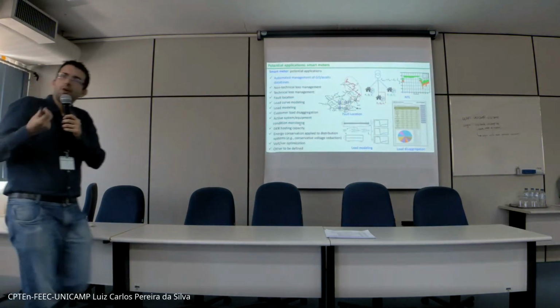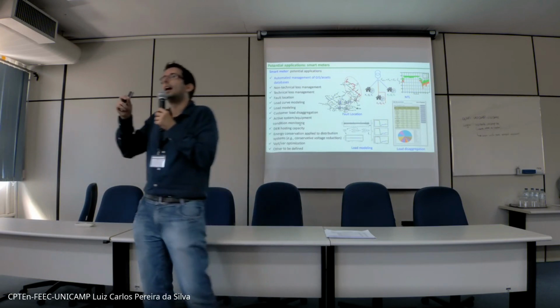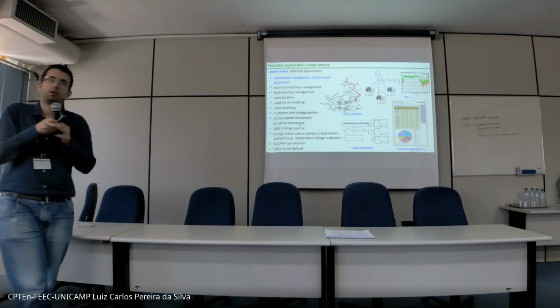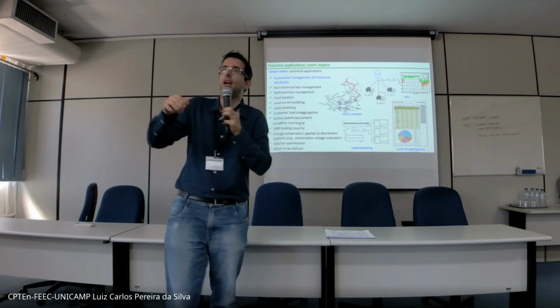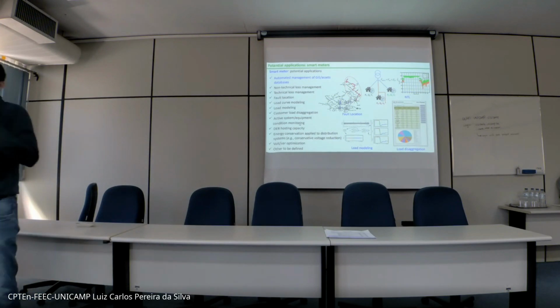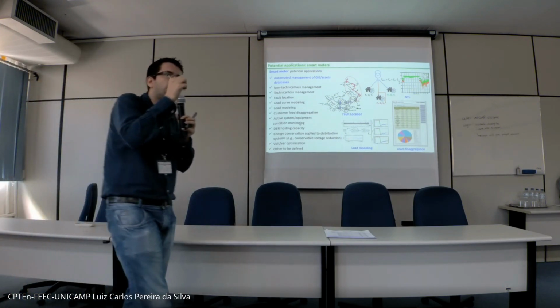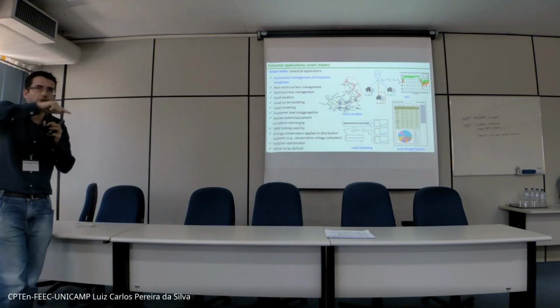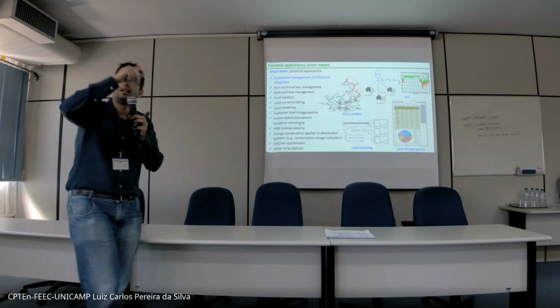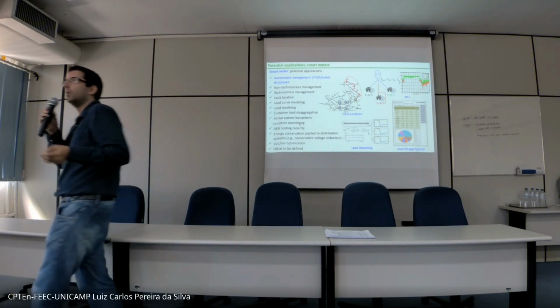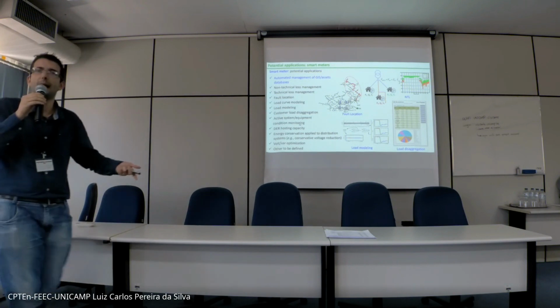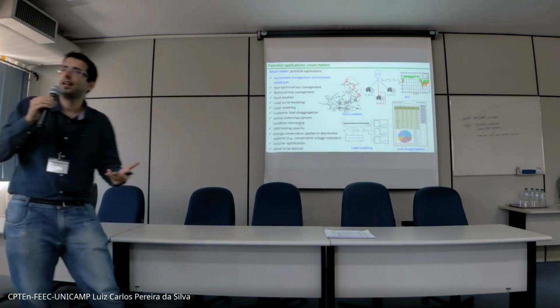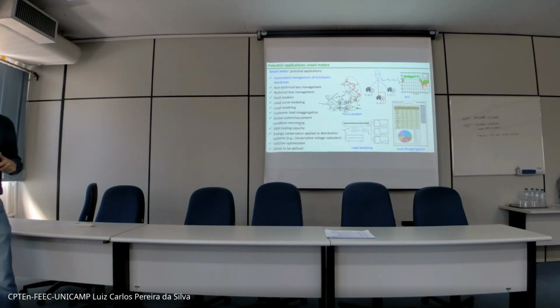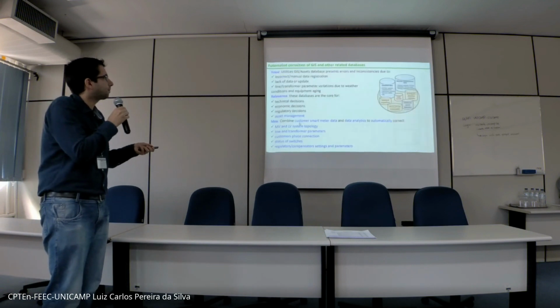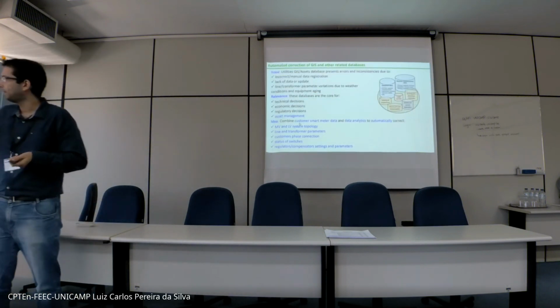DER hosting capacity, system condition monitoring. With increased data, you can predict failures in the system, because a failure in a transformer, capacitor bank, or cable does not happen suddenly. It starts sending small signals, small signatures. If you watch the voltage and current waveforms, it starts creating distortions for weeks or even months before an actual failure happens. So if you are monitoring and analyzing this data, you can avoid failures in system components.